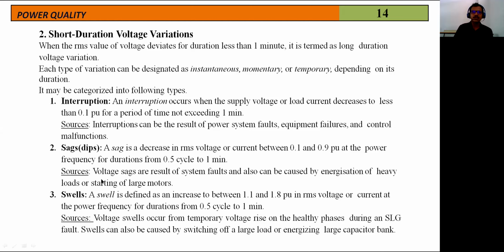Sources: voltage sags are a result of system faults and also can be caused by energization of heavy loads or starting of a large motor. Suddenly, a large motor is switched on, so the voltage starts decreasing. There is a dip in the voltage. Energization of heavy loads: if you apply heavy loads suddenly, there is a drastic increase in the current, and therefore a drastic change in the voltage. That is called a dip.